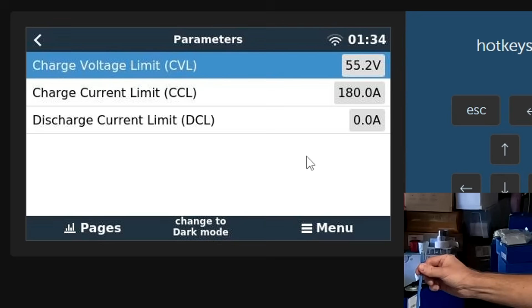Unplug the slave. Slave has got a fault, battery has turned off or something. Does it still tell the inverter to charge with 180 amps? I've got the cable here in my hand. The slave is not plugged in. Whoa, that is so bad.